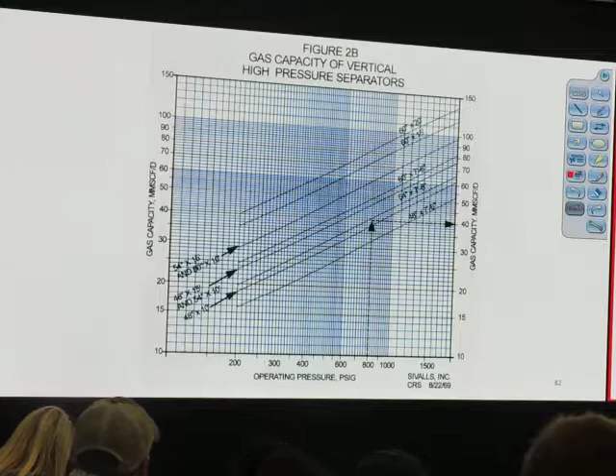The way to read the chart is you need to read this first. That's it, very easy. And we have several charts: gas capacity and liquid capacity. We have to check both. For a vertical separator, we check both gas capacity and liquid capacity. It should handle both the gas phase and the liquid phase. For a horizontal separator, we check gas capacity, so this one is called gas capacity, and we check liquid capacity, so this one is liquid capacity. We check both of them.